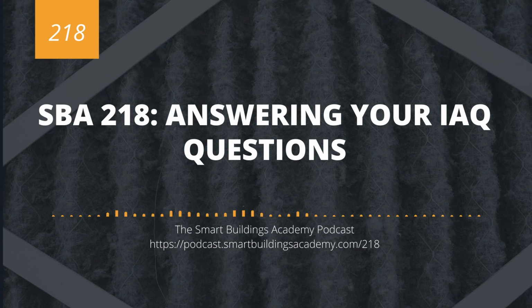Yes and no. So let's answer the yes, and then let's answer the no. So are certain systems more amenable to IAQ? Yes. I mean, if you have a building automation system that is newer, you should, as long as you have the programming tools, be able to implement strategies around IAQ. You may not have the sensor density to do the logging that you need, so you may not be able to do some of the humidity control. You may not have humidifiers and dehumidification sequences, but for most of them, you can go and make the code changes.